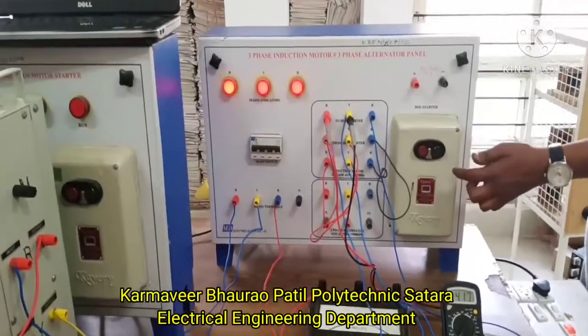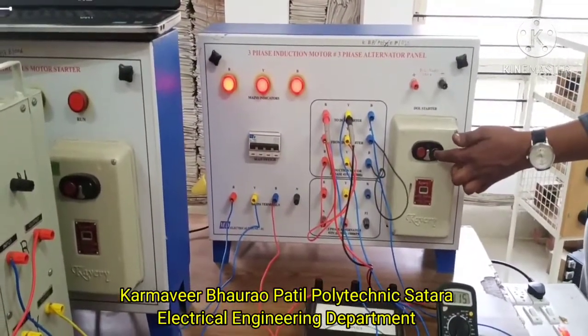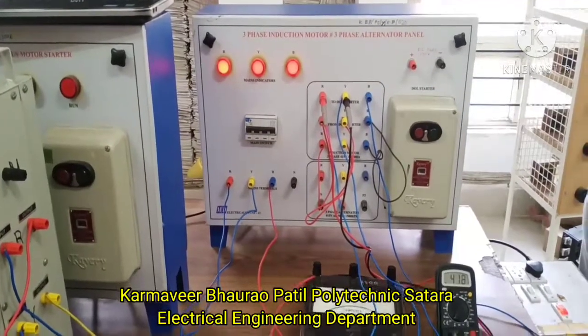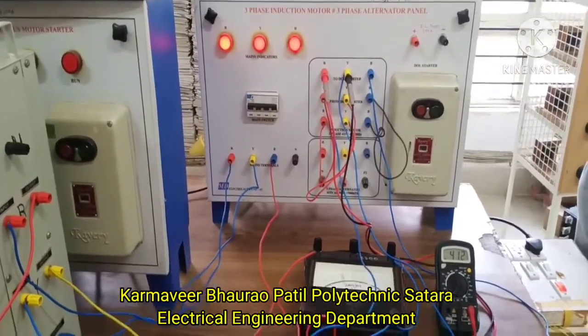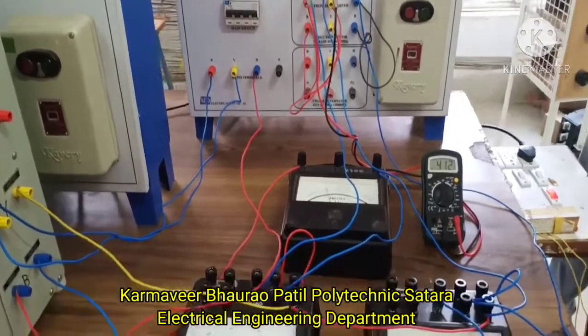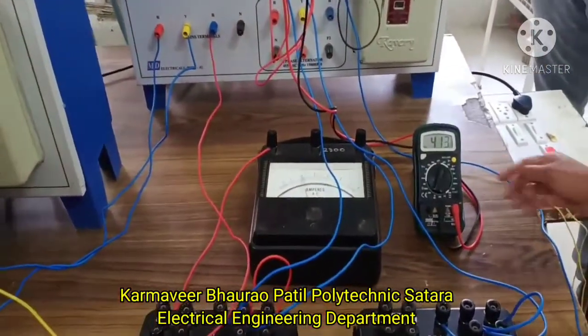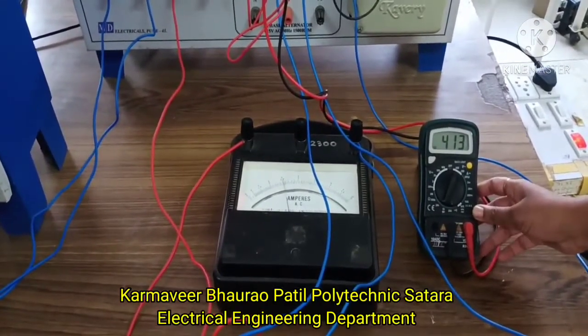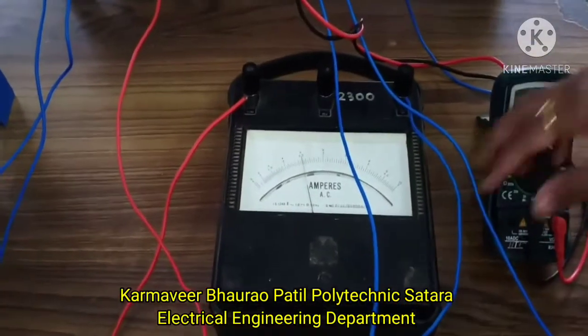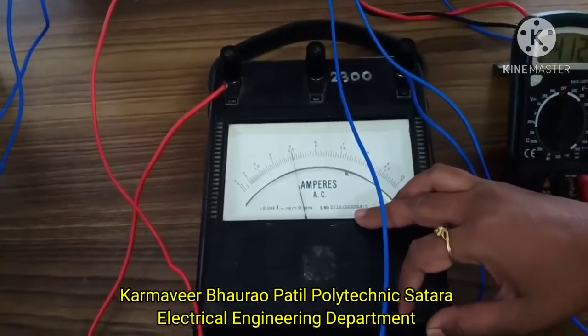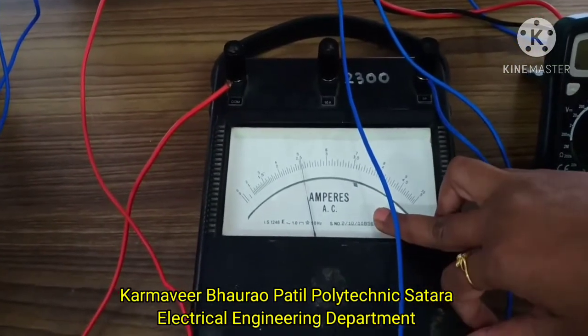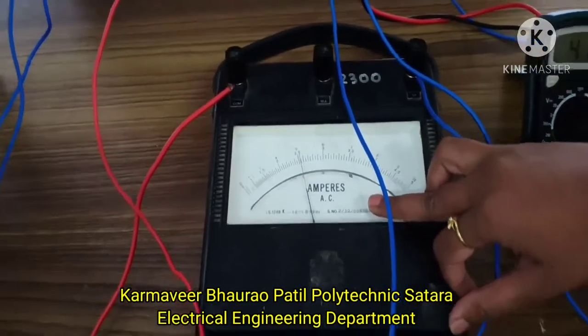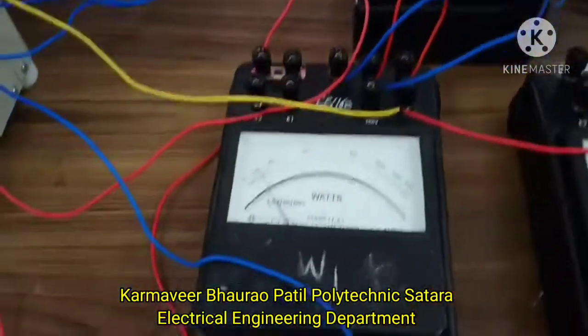We have to switch on the motor starter connection. First we will observe that we have applied the rated voltage, so we will note down the reading for V0 as 412 volt. Then we will note down the reading for I0, that is 2.5 ampere. So our I0 is 2.5 ampere.